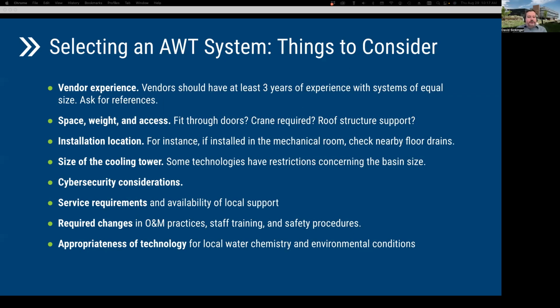So the next 2 slides are actually going to cover a variety of things to consider when selecting an AWT system. I suggest asking for references, and ideally for systems of equivalent size that have been operating over a few cooling seasons. When you are selecting one, you do want to take into account the space, weight, and access conditions for your site. Ask yourself, will it fit through doors?